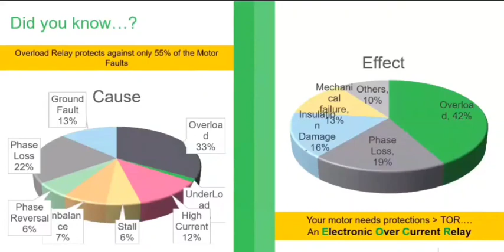When I talk about protections, on the right hand side you will see a chart which speaks about the different protection levels. For example, over current, under current, phase loss, stall condition, phase reversal, unbalance, even ground fault protection can be achieved with this EOCR. The very first thing after a motor trips is fault differentiation. The customer needs to know the exact reason for the motor failure, how to incorporate that into the next scheduled maintenance action, and what downtime is required to restart the process again.